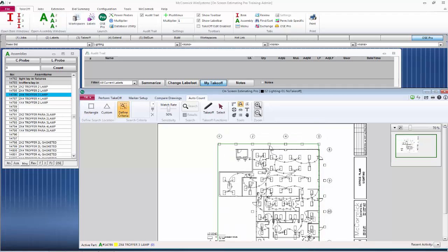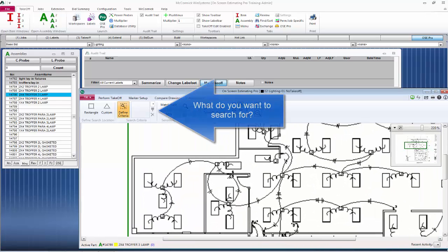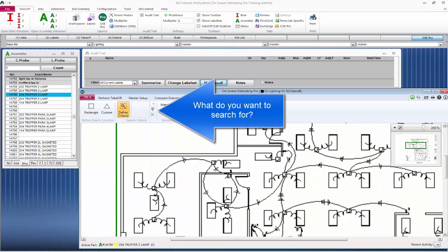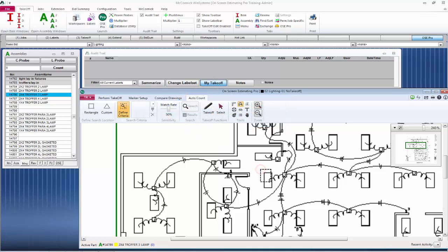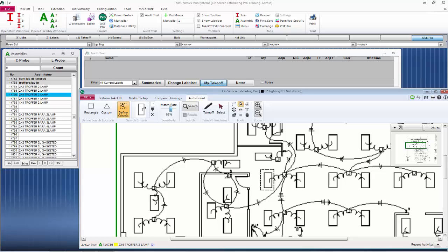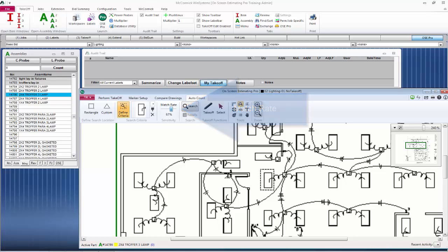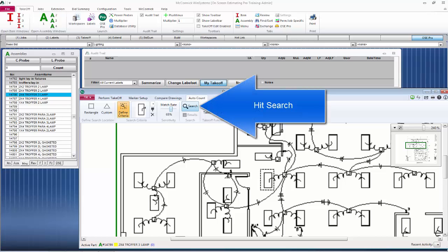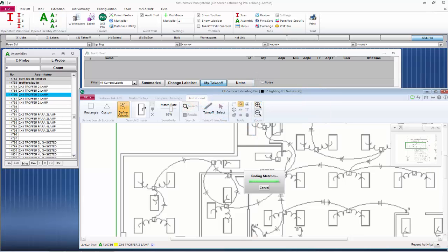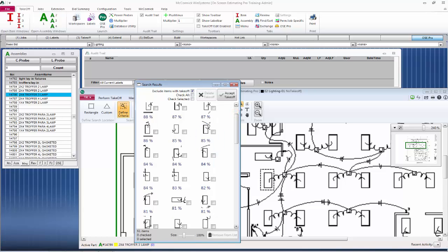Next we're going to want to define the criteria. This is what we're going to be searching for. So it is a fixture. I'm going to draw a box over the fixture here in the middle of the screen. That's going to put the drawing up into our search criteria. Next pick a match rate. This is something you're going to become comfortable with as time goes on. I suggest starting at about 65 to 70 percent. That's it. Hit search and the program will go through and try to find all those fixtures for you.